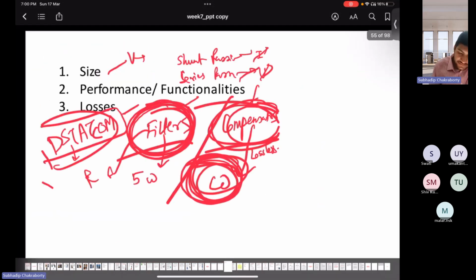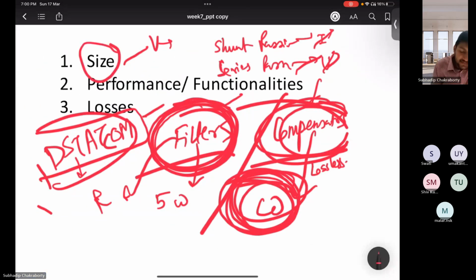So in terms of size, I can tell you, for example, the active compensators, they are of huge size, right? The converters. But the filters are small in size, right? Because they are designed for higher frequencies, and to block higher frequency or higher harmonics, you need a small amount of L and C, and to provide the low impedance to those harmonics. And performance, by functionality, obviously these compensating devices are much more superior, because they can actually accompany the system with multiple harmonic contents.